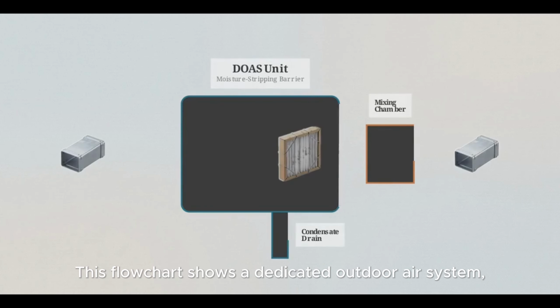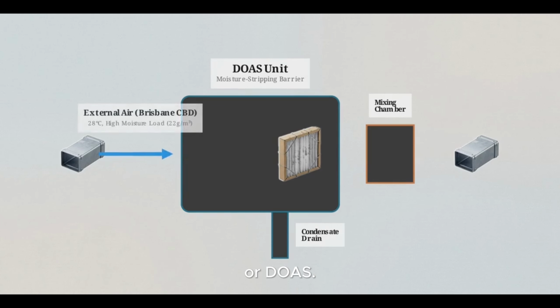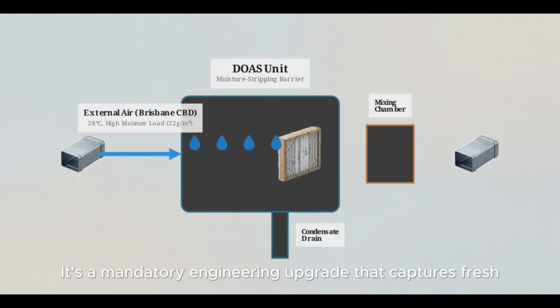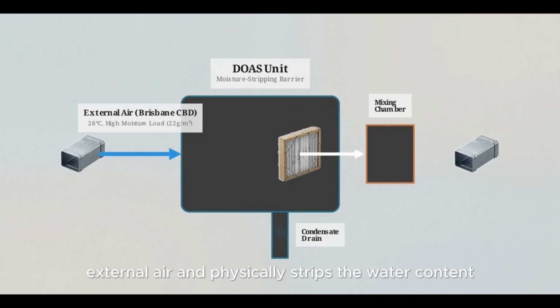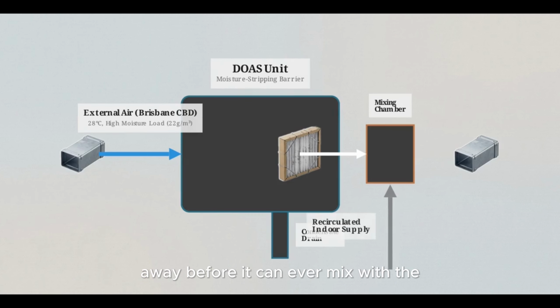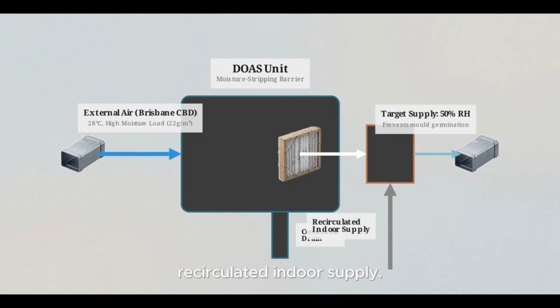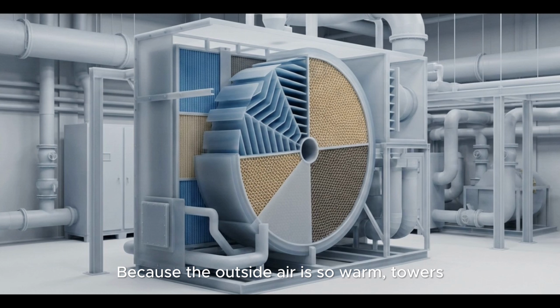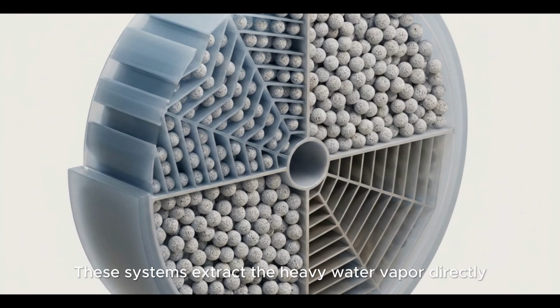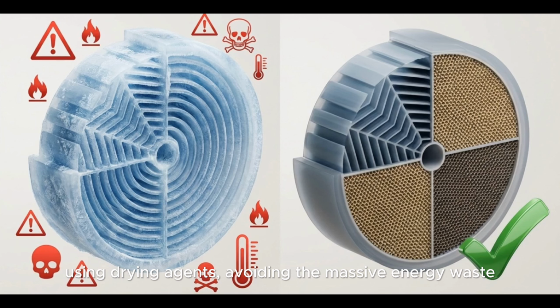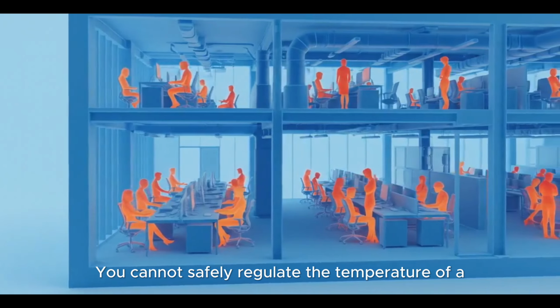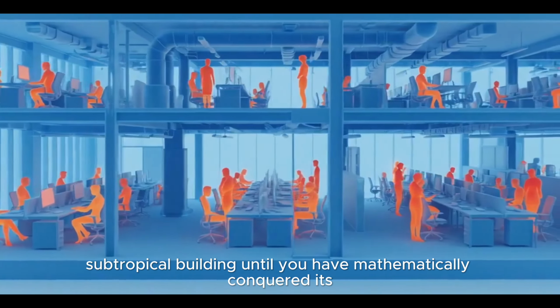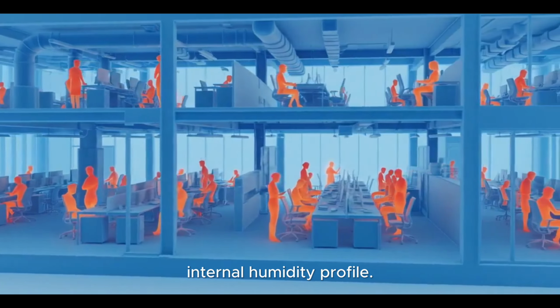This flowchart shows a dedicated outdoor air system, or DOAS. It's a mandatory engineering upgrade that captures fresh external air and physically strips the water content away before it can ever mix with the recirculated indoor supply. Because the outside air is so warm, towers here rely on specialized desiccant dehumidifiers. These systems extract the heavy water vapor directly using drying agents, avoiding the massive energy waste of trying to freeze the humidity out of the air. You cannot safely regulate the temperature of a subtropical building until you have mathematically conquered its internal humidity profile.